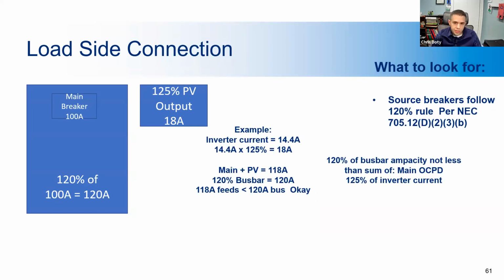So here's a simple look at the common load side connection calculation that I just mentioned, the 120% rule. That's to determine if the panel board is large enough to accommodate the PV system. So you want to ensure that the main breaker plus 125% of the PV output current does not exceed the bus bar rating by more than 120%.